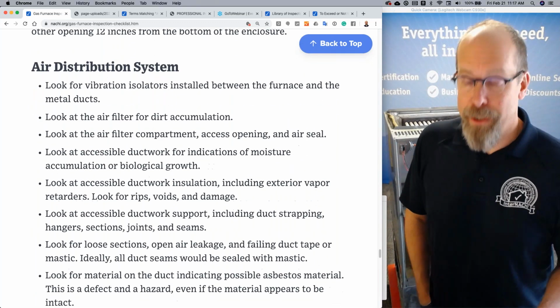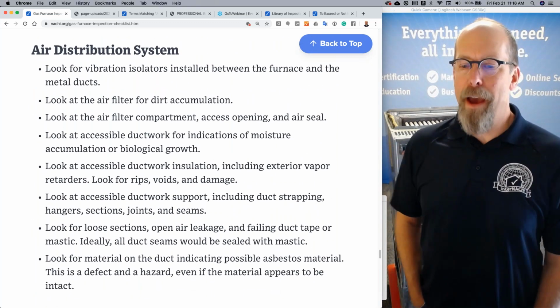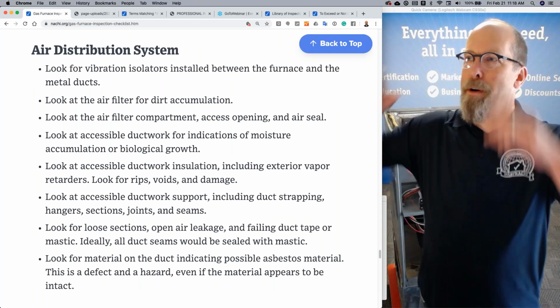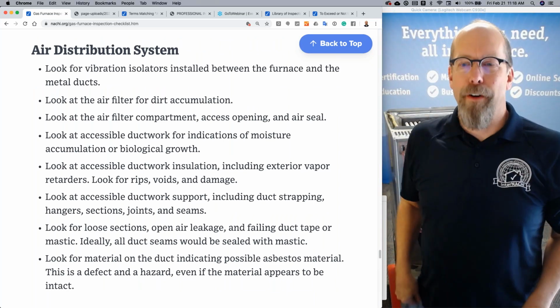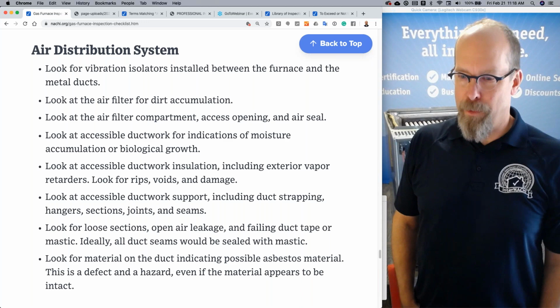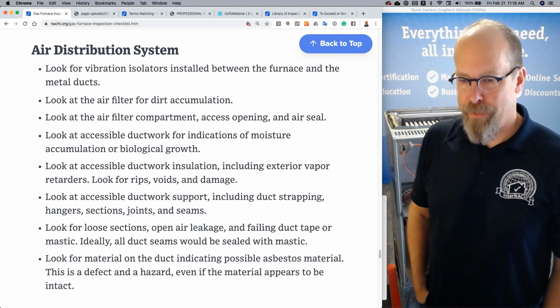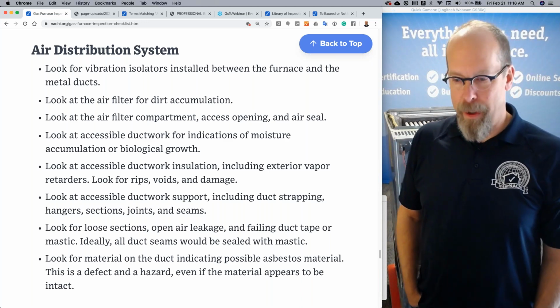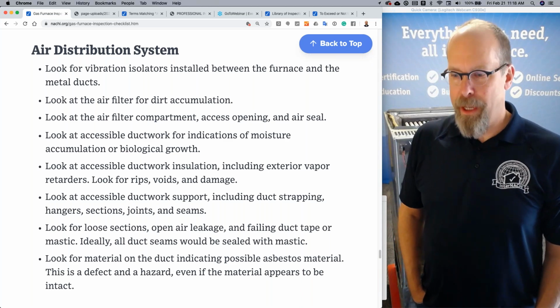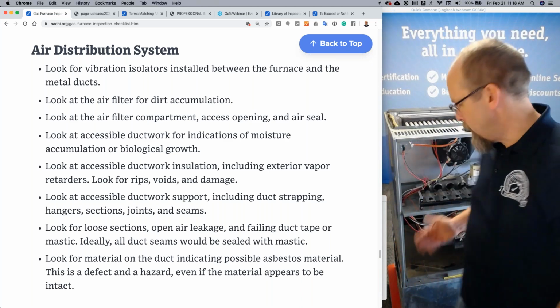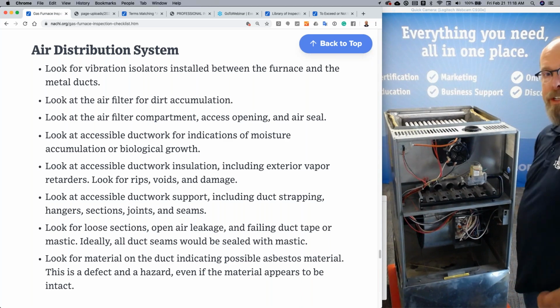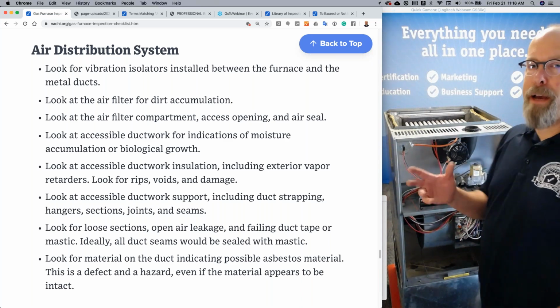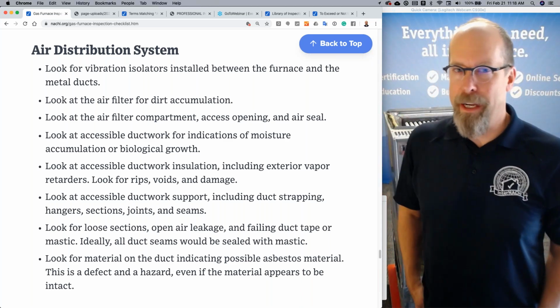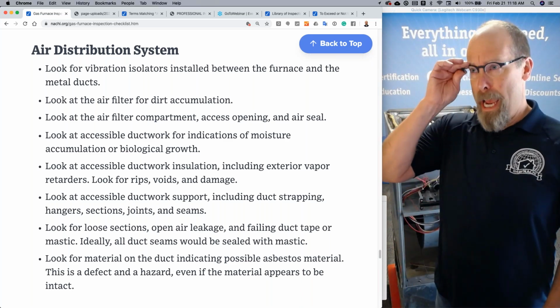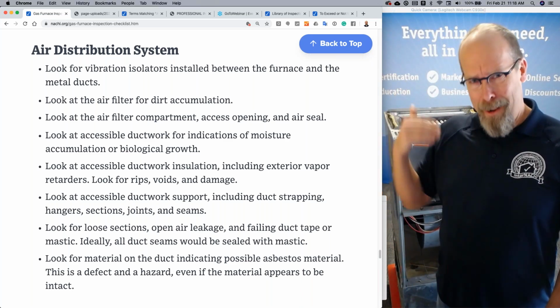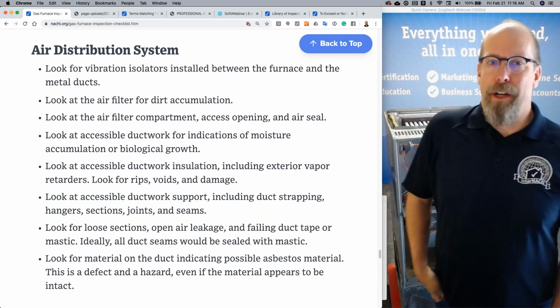Air distribution systems. Look for vibration isolators. That's that rubber stuff at the top of the furnace, between the furnace itself and the ductwork. Look for the air filter for dirt. Look at the air filter compartment, the access opening, and the air seal if it's installed outside of the cabinet in the ductwork at the return. Sometimes those are completely open, and you don't want that, right? You don't want essentially a return register next to a furnace that needs combustion air.